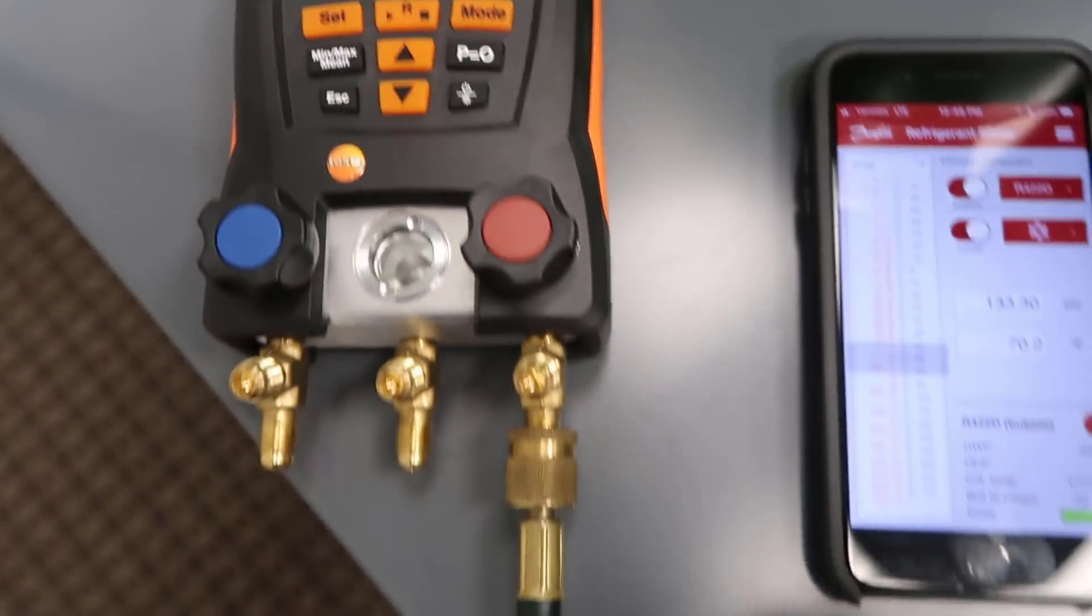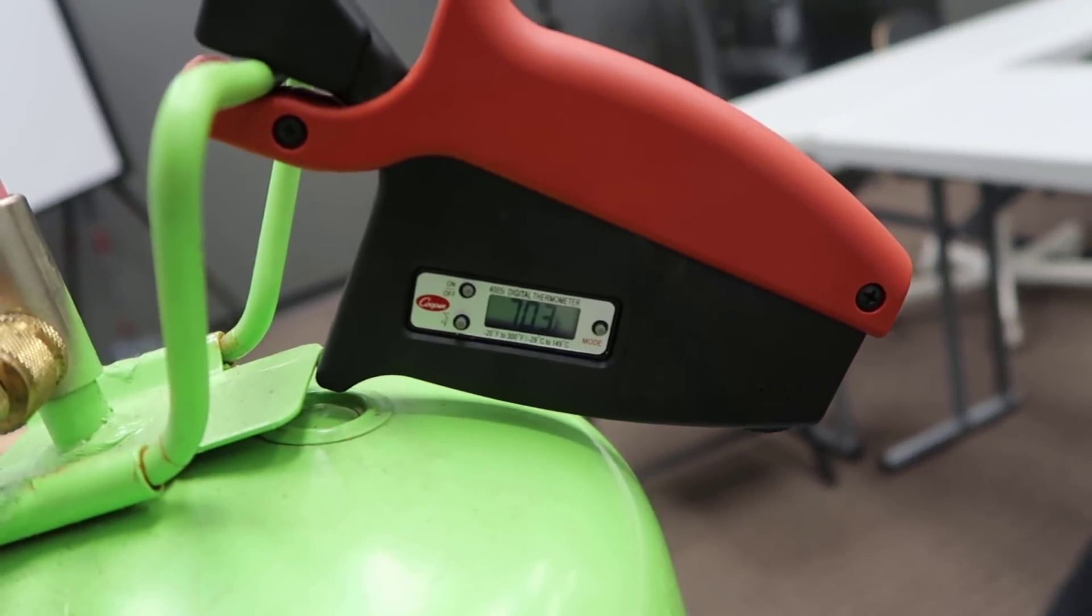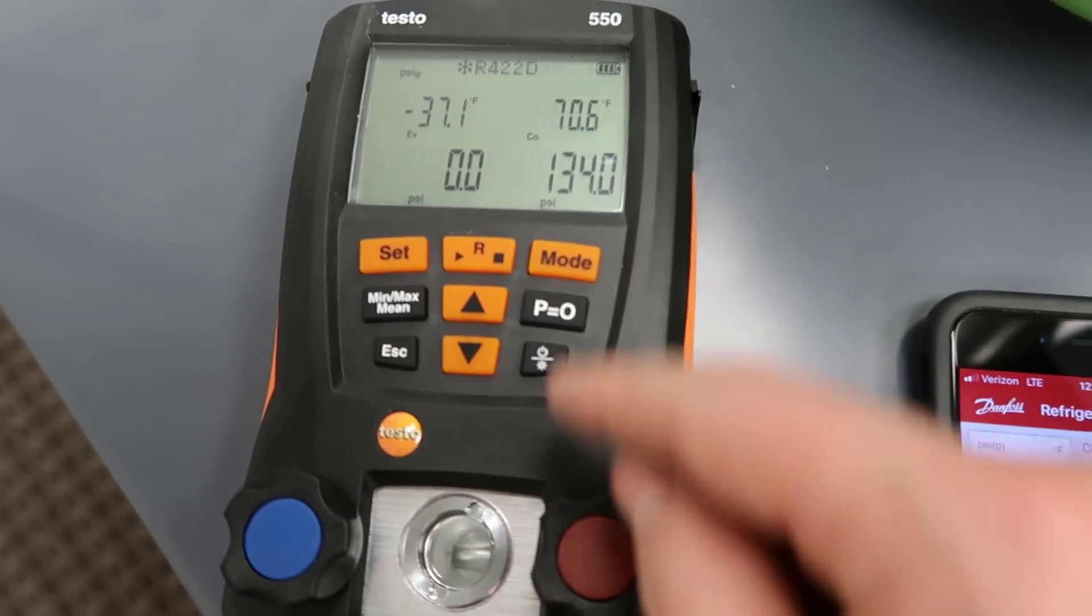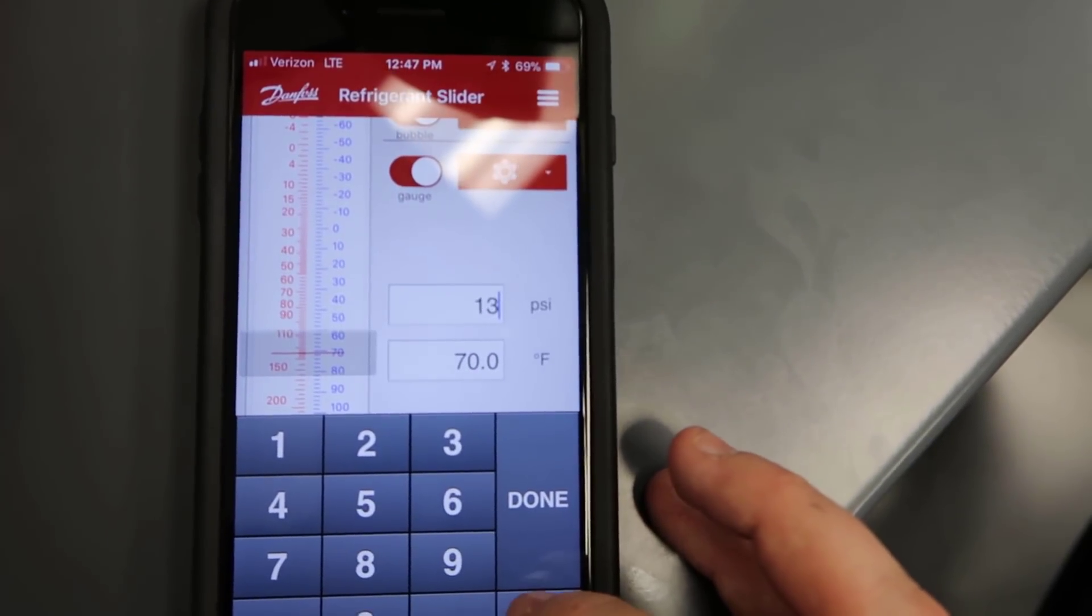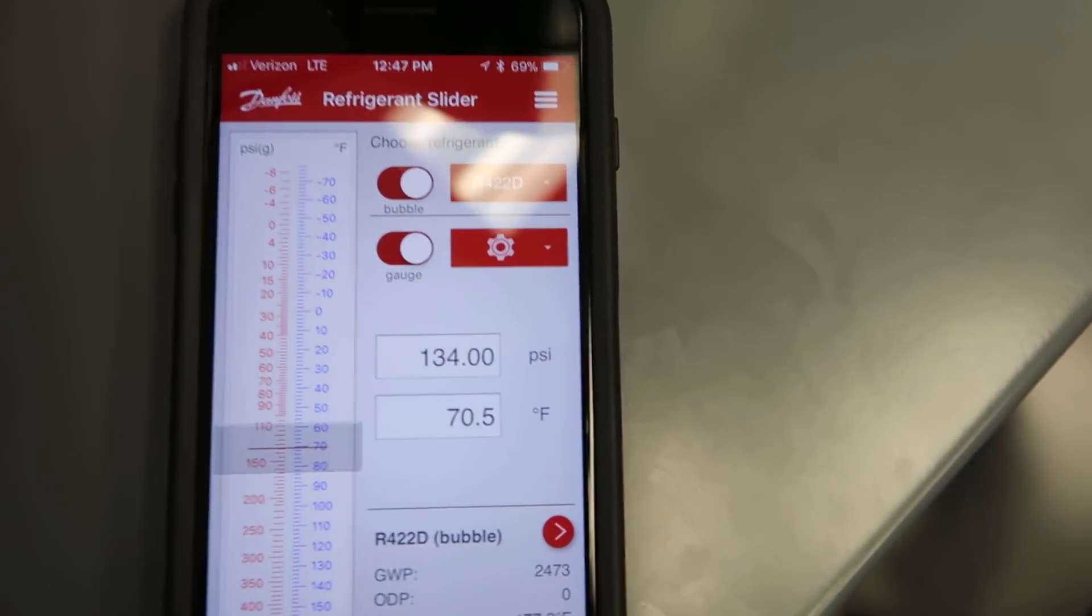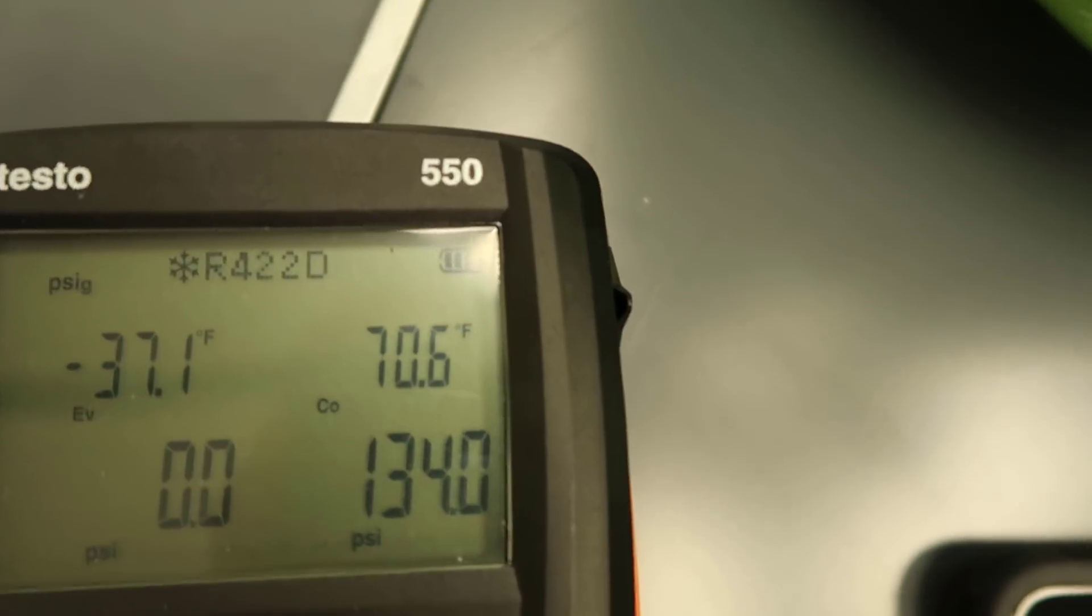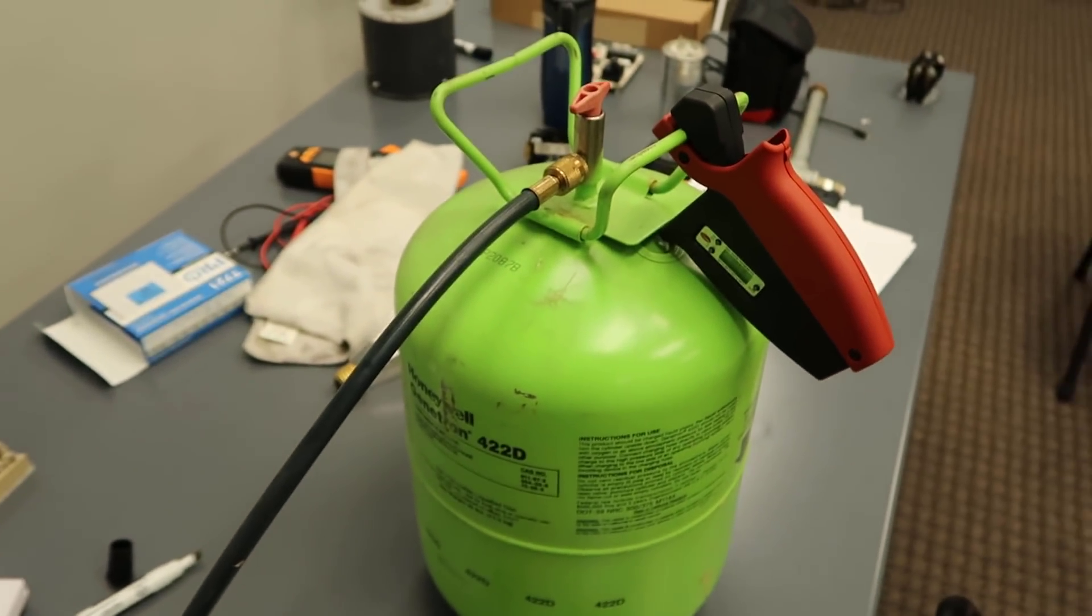I've got this connected to a set of Testo 550s. I've got a tank of Honeywell Gentron 422D. You can see the ambient temperature of this tank is 70.3 degrees, which matches up very closely with a connection to the high side. Testo is automatically looking for the bubble point because it's looking to calculate subcool. If I go over here and I punch in this pressure, 134 psi on the Danfoss refrigerant slider app, you'll see that it matches right up, 70.5, so within a couple tenths of a degree. Now, if I change it over to dew, you'll see that it's significantly higher, 75.8. So it's clearly not dew point. This tank is clearly not at dew point in its static state. It's at bubble point, and it is not at the average temperature.